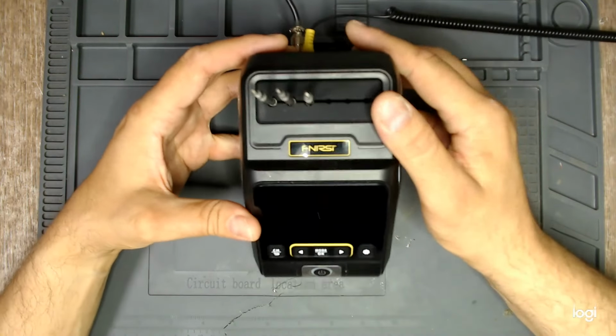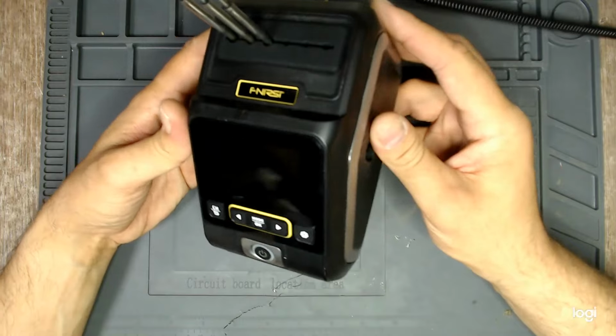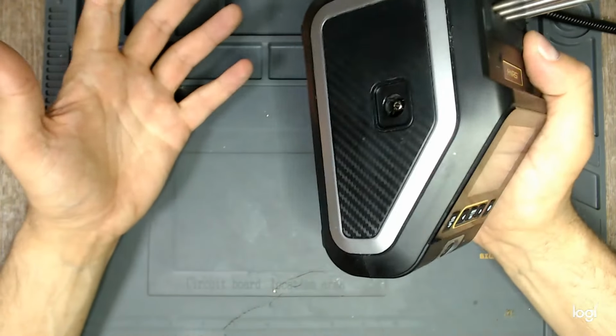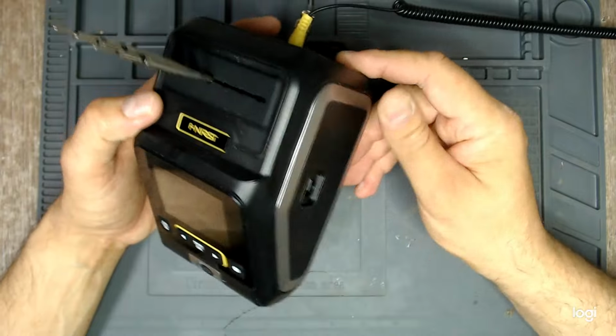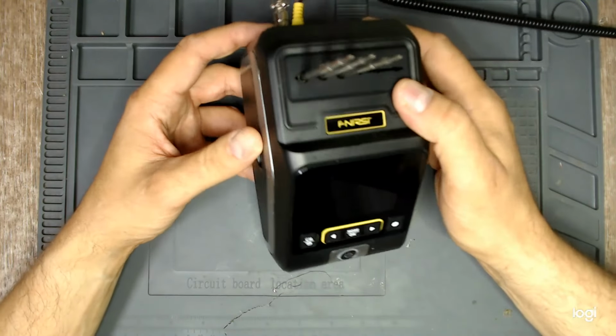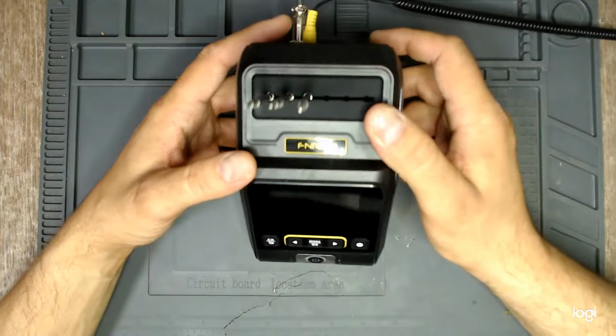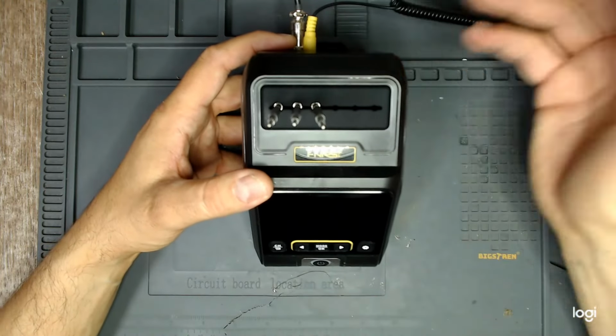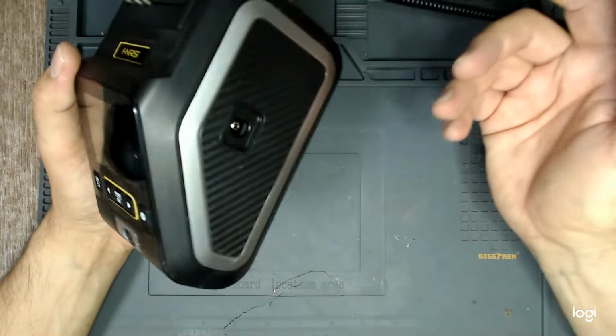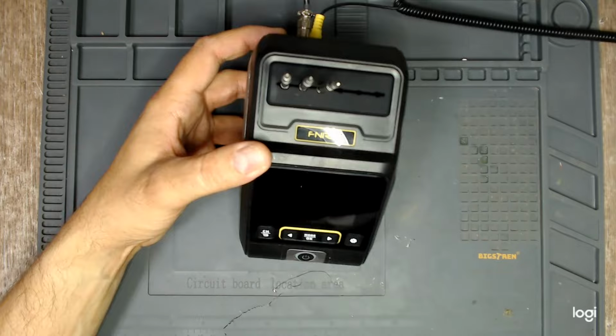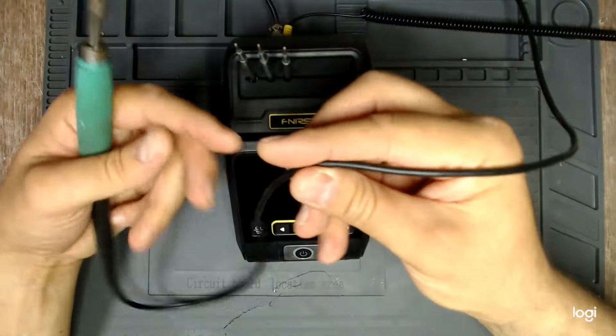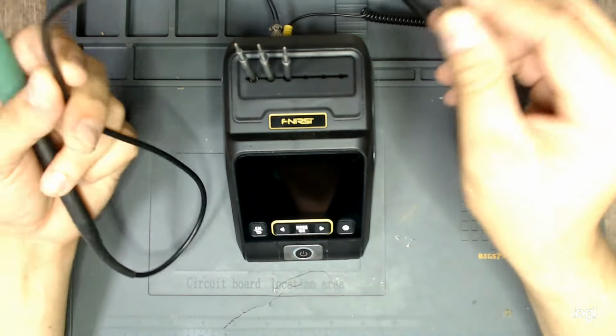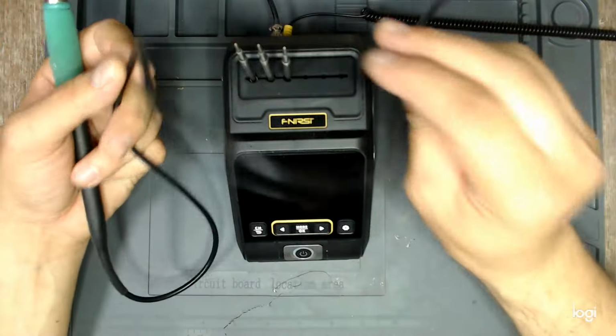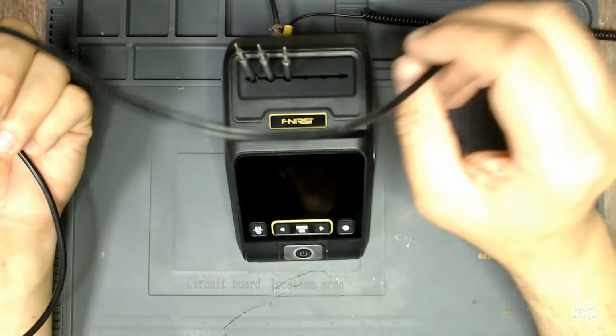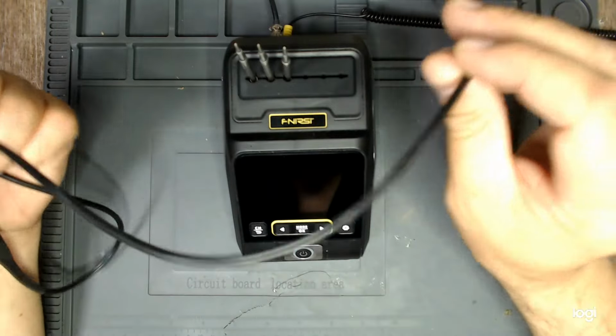What do I want to test? I want to start with the power supply module itself. Have a look at it, test it under load, use the oscilloscope to see what, if any, leakage is on the output between the ground and the earth. Then I want to measure the handle wires' resistances and see how much loss could be on them, and test the leakage on the tip and so on.